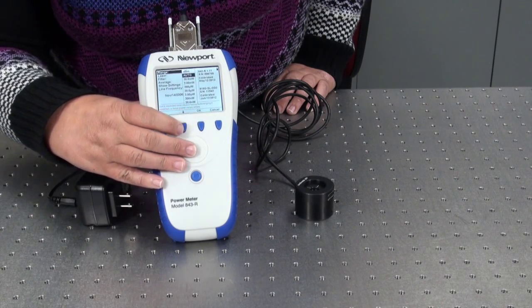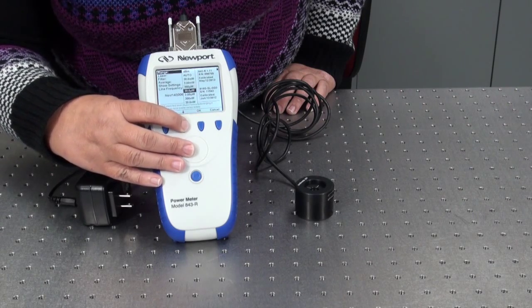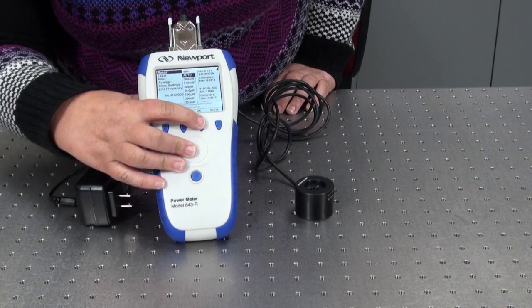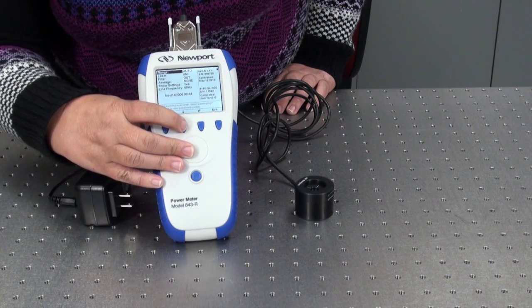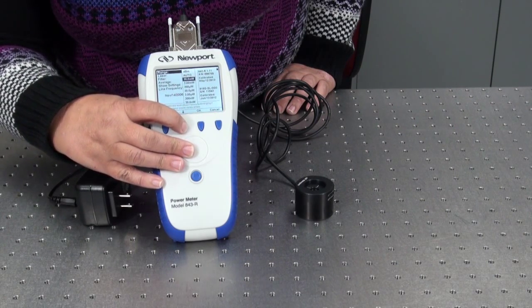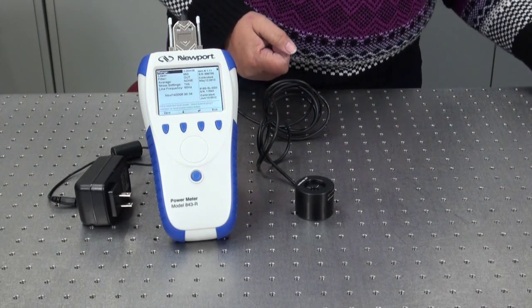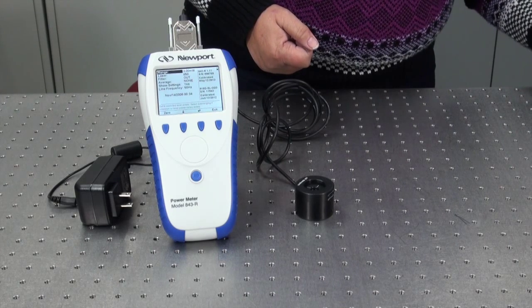The range menu allows you to select between auto-ranging and manual-ranging. Select manual-ranging if you know your light source power, then select the correct range for measuring that power. Select auto-ranging if you are not certain of the power of your light source or if you will be measuring through a broad power range.